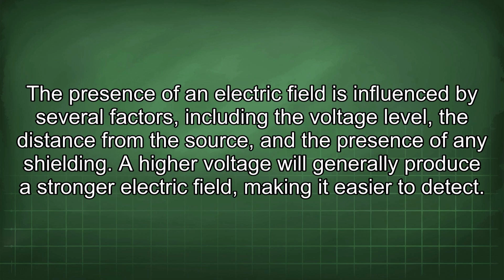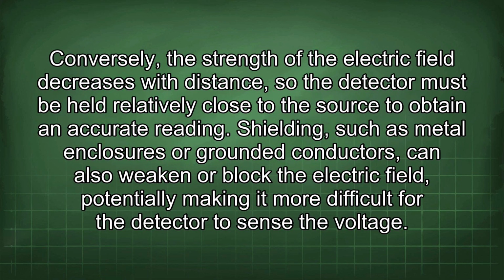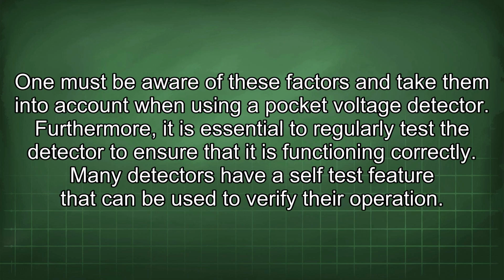The presence of an electric field is influenced by several factors, including the voltage level, the distance from the source, and the presence of any shielding. A higher voltage will generally produce a stronger electric field, making it easier to detect. Conversely, the strength of the electric field decreases with distance, so the detector must be held relatively close to the source to obtain an accurate reading. Shielding, such as metal enclosures or grounded conductors, can also weaken or block the electric field, potentially making it more difficult for the detector to sense the voltage. One must be aware of these factors and take them into account when using a pocket voltage detector.